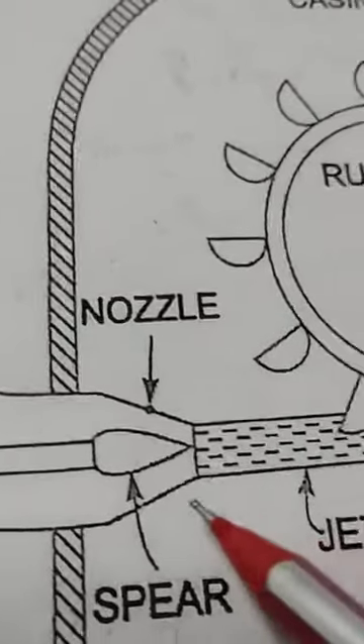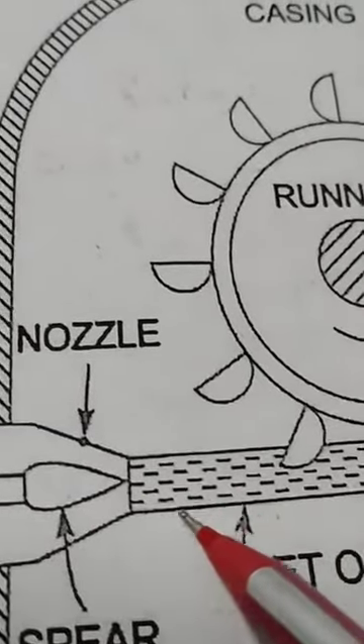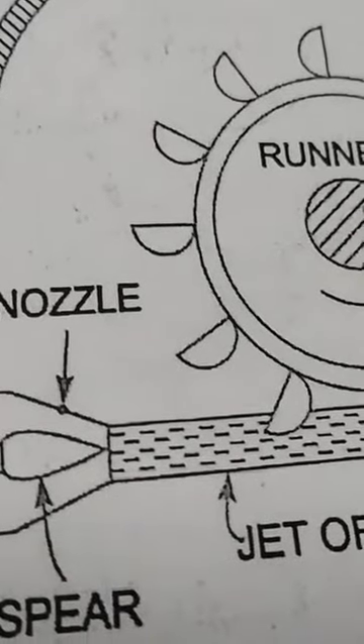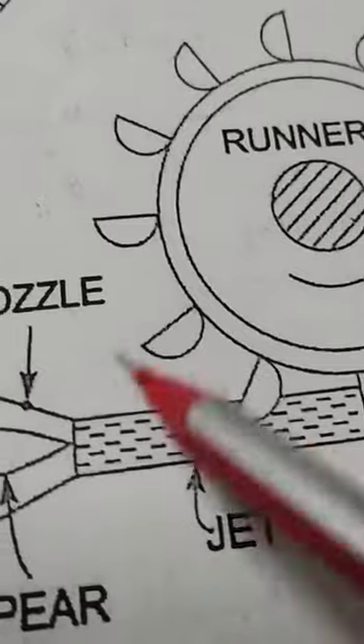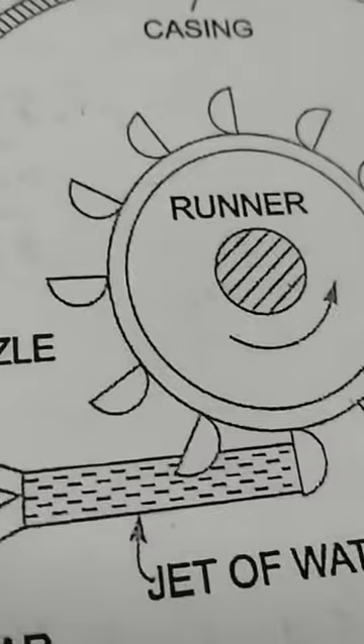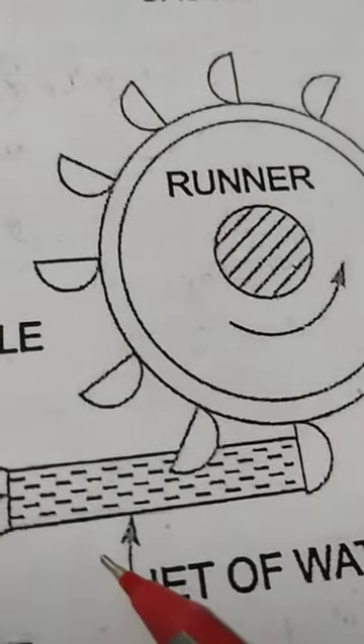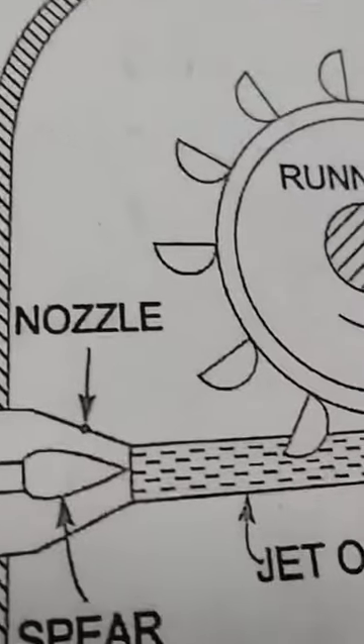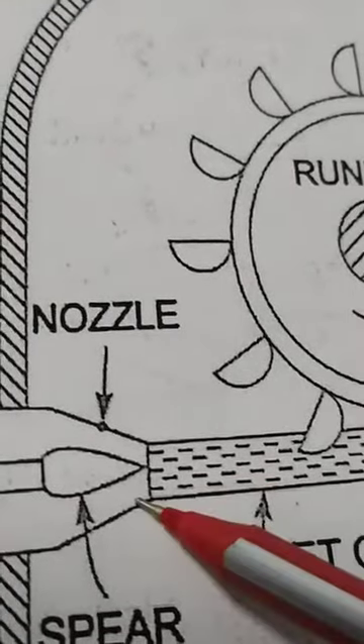Coming to overall efficiency, I take from first to last: the first power is water power and the last is shaft power. The ratio of shaft power to water power is called overall efficiency. To summarize: runner power to water power is hydraulic efficiency; shaft power to runner power is mechanical efficiency; shaft power to water power is overall efficiency.